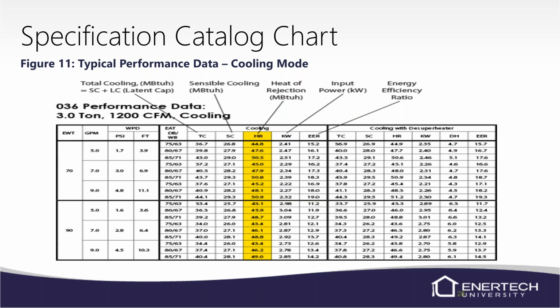So we're removing heat from the home. We remove heat from the home, add the heat of compression, and put all of that back into the loop field. And that's why heat of rejection will always be higher than your heat of extraction. But the calculation that we do to get to our heat of rejection is the exact same. It'll just always be higher.